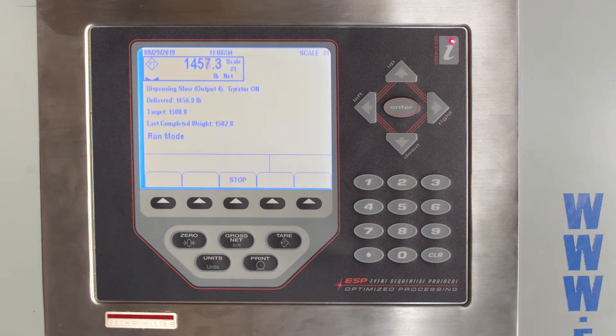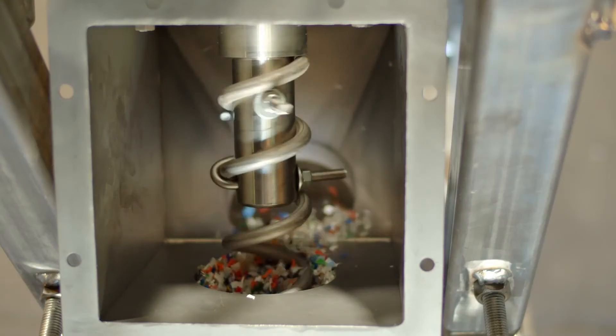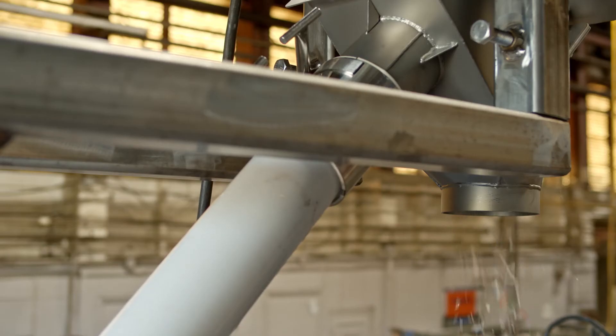the system will partially close the valve to dribble or slow the conveyor. The controller will close the valve or stop the conveyor just prior to the target weight to account for in-flight material.